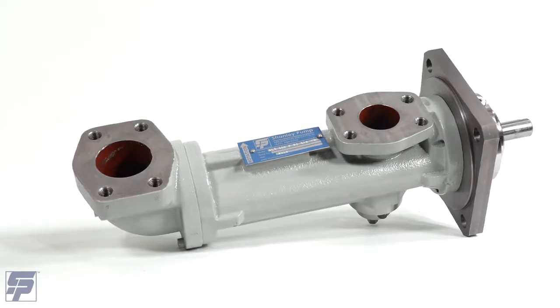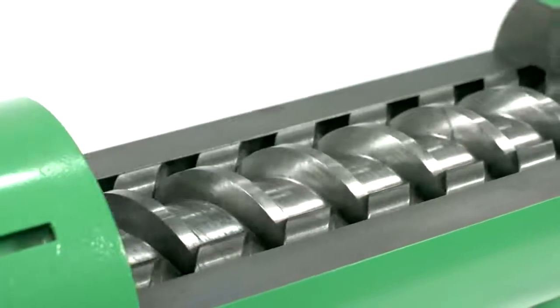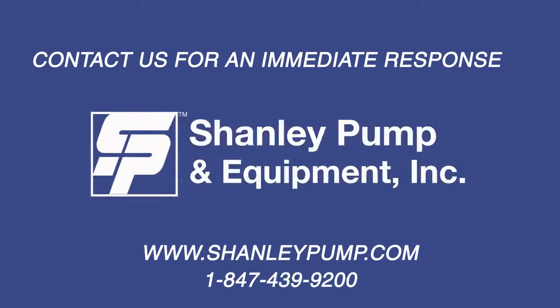Your PXF or 3LS three rotor screw pump is now fully assembled. Check to make sure the pump turns freely. The pump should then be leak tested using water to check the shaft seal and casing O-rings for leakage before being reinstalled and put into service. If no leaks are present, the pump can now be reinstalled into the pump system. If you have any questions or require spare parts for the repair of your Shanley PXF or Shanley 3LS pump, please feel free to contact us at www.ShanleyPump.com or call 847-439-9200. We always have complete pumps and all spare parts in our inventory ready to ship the same day.